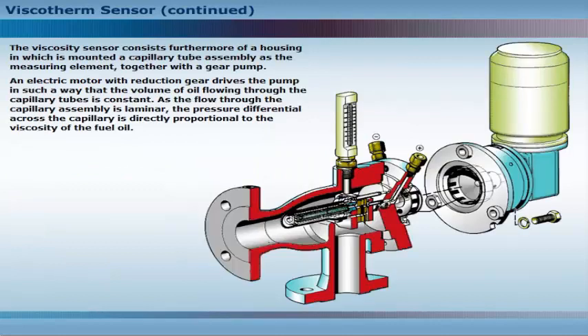The viscosity sensor consists furthermore of a housing in which is mounted a capillary tube assembly as the measuring element, together with a gear pump. An electric motor with reduction gear drives the pump in such a way that the volume of oil flowing through the capillary tubes is constant. As the flow through the capillary assembly is laminar, the pressure differential across the capillary is directly proportional to the viscosity of the fuel oil.